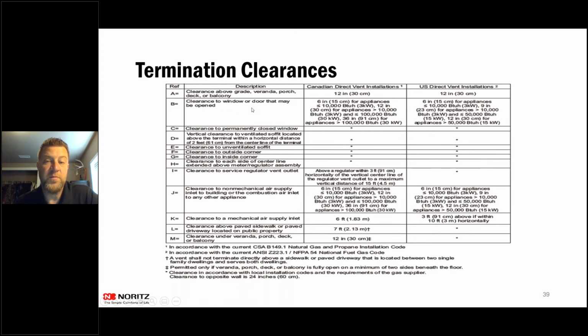Clearance to a window or a door that can be opened. Say you were installing a power vent water heater that was only 40,000 BTUs: anything that is 50,000 BTUs or lower, you would only need to have a 9-inch clearance. But with tankless, you're going to be above 50,000 BTUs all the time, which is a 12-inch clearance. So for any window or door that can be opened, that is a 12-inch clearance.